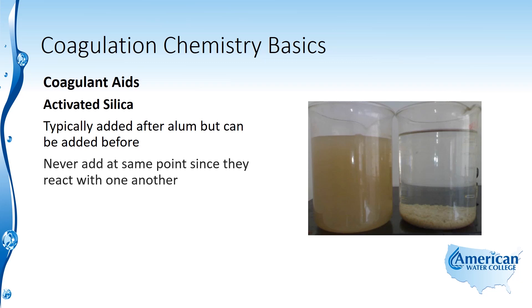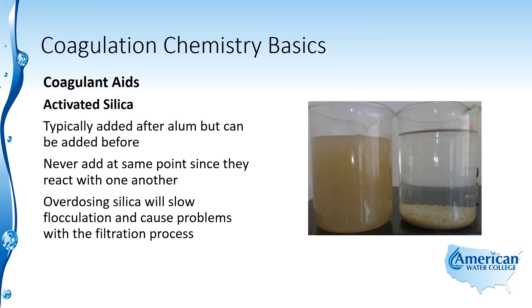You don't want to add alum and activated silica at the same point since they react with one another, which would be counterproductive. Typically you add the alum first, then the activated silica once the alum has had a chance to perform its coagulation function. If you overdose silica, it will slow the flocculation process and cause problems with filtration — too much of a good thing can be a bad thing.